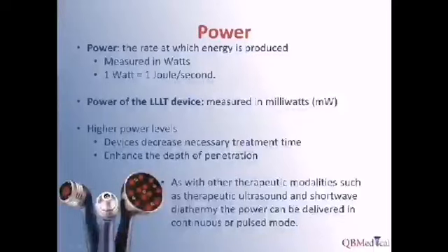The next parameter we need to be concerned with is power of the device. Power is the rate at which energy is emitted from the applicator. In low-level laser therapy devices, this is measured in milliwatts, and the reason we need to be concerned with power is it's going to affect other parameters of the treatment.